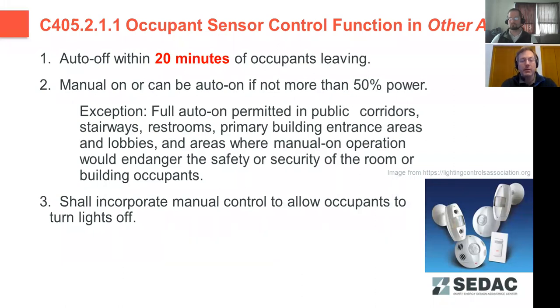So with that covering the warehouse areas and the open plan offices, now we get into everywhere else that is not those two. So here, noting the auto off within 20 minutes of occupants leaving a space. Previously, in the previous code cycles, that was 30 minutes. So this is a reduction. Also, it's noting that this can be manual on, or if it's auto on, it cannot bring on more than 50% power. So manual on typically would be called vacancy sensors, where auto on would typically be considered occupancy sensors.